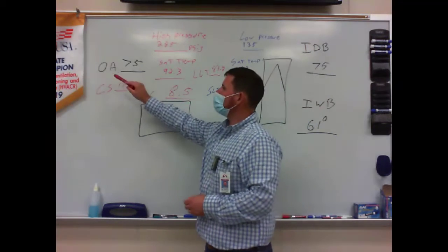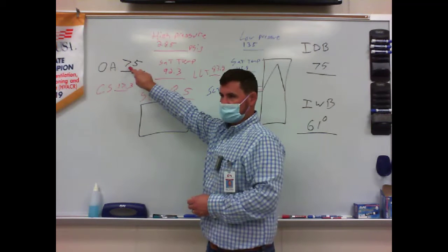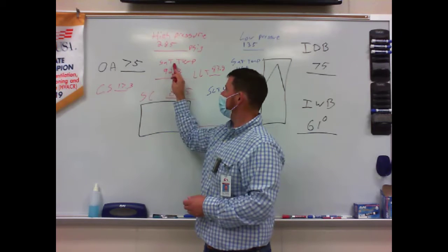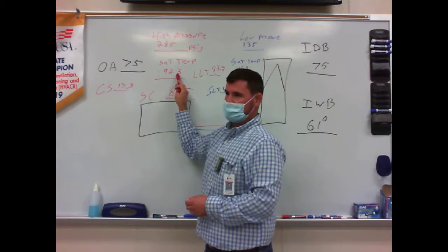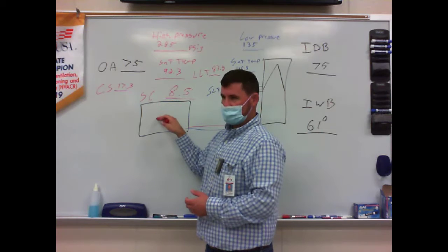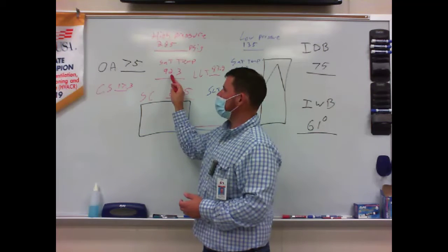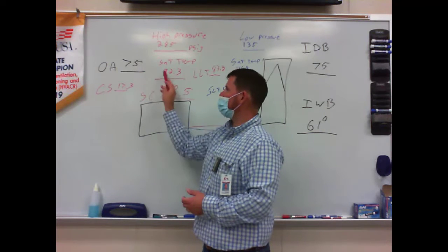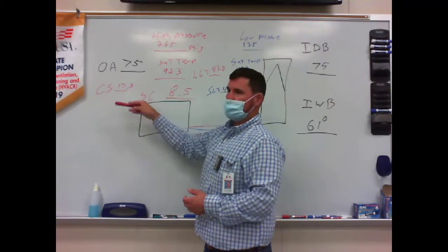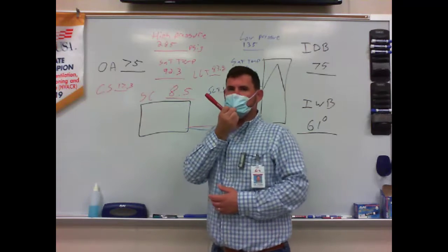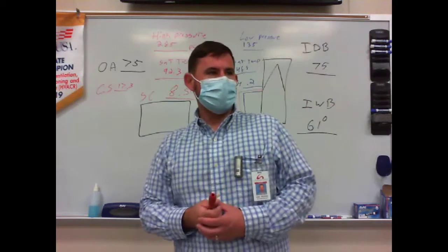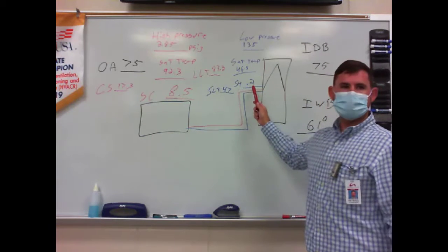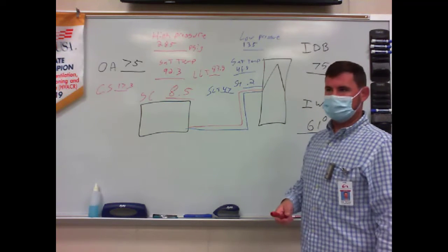All right, so what I'm really doing is I'm saying I'm 75 degrees outside, right? How warm was my condenser? Well, I was saturating at 92 degrees. Remember, that condenser's got to be warmer to get rid of that heat, right? So how much warmer was my condenser than the air? I just subtract my smaller number from my bigger number, and come up with 17.3 degrees. That's not a terrible number, right? That's pretty close to 20. But the number that is terrible is 0 degrees of superheat.